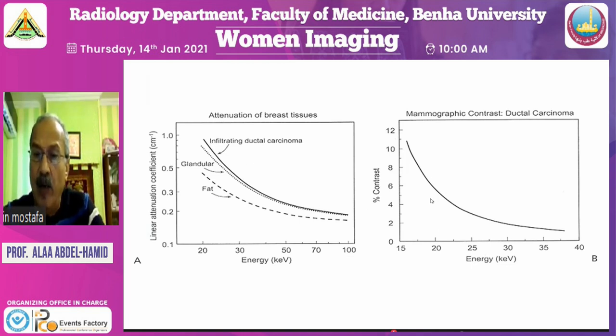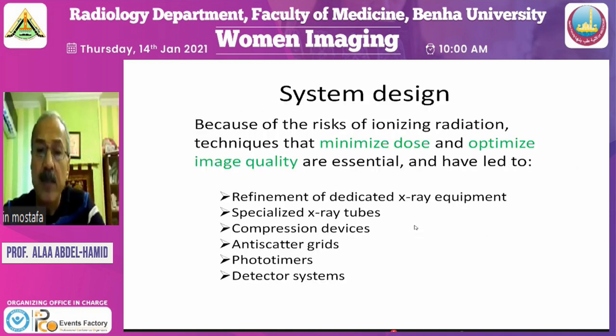Also, the mammographic contrast increases at the very low kilovolt technique of the breast. The system design here, because of the risk of ionizing radiation technique, the target of mammography was to minimize the dose and optimize the image quality. Here, we have to use the refinement of the dedicated X-ray equipment, specialized X-ray tubes, compression devices, very important, anti-scatter grid, photo timers, and detector system.